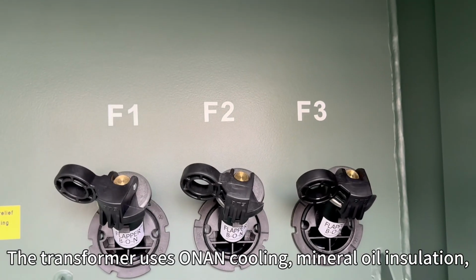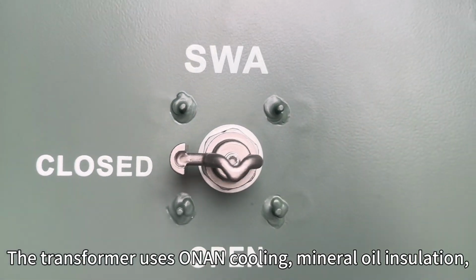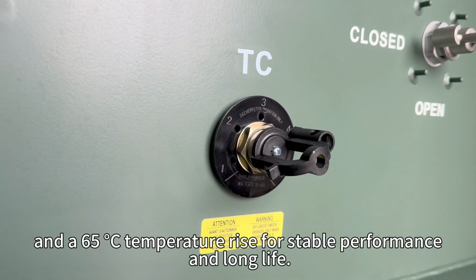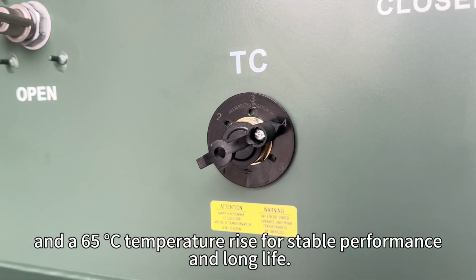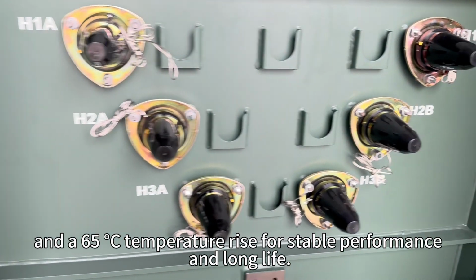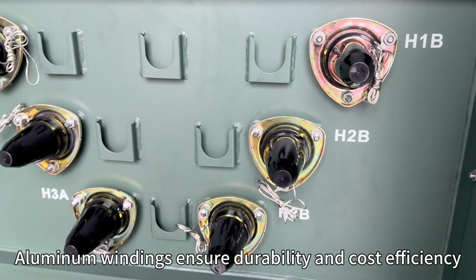The transformer uses ONAN cooling, mineral oil insulation, and a 65°C temperature rise for stable performance and long life. Aluminum windings ensure durability and cost efficiency.